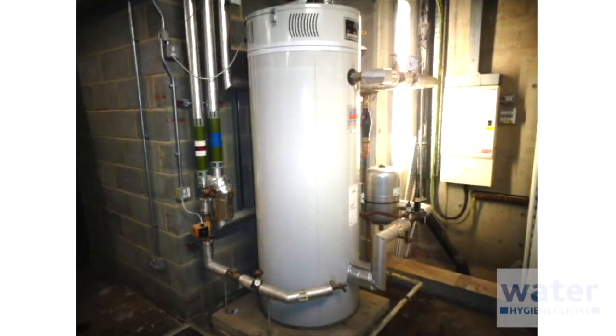Now let's have a look at temperature monitoring from a typical flow and return hot water generator. Using your surface probe, take a flow temperature from the flow pipework. Next, we take the temperature from the return pipework. If there is a pump present, this can sometimes transfer heat, so make sure you take the temperature from an appropriate distance from both the pump and the hot water generator.